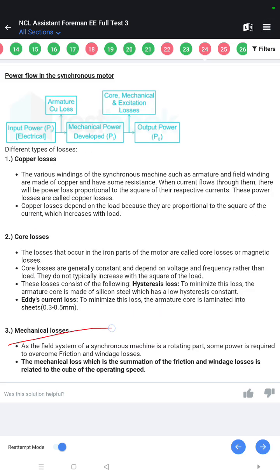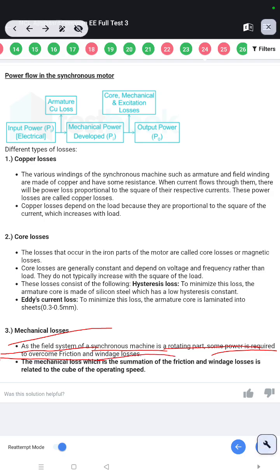Mechanical losses. As the field system of a synchronous machine is a rotating part, some power is required to overcome friction and windage losses. The mechanical loss, which is the summation of the friction and windage losses, is related to the cube of operating speed.